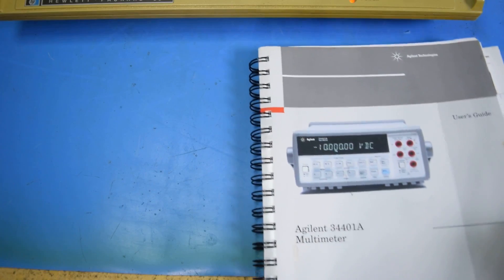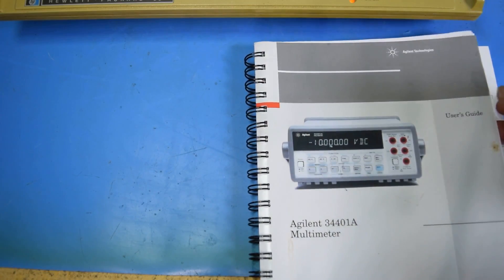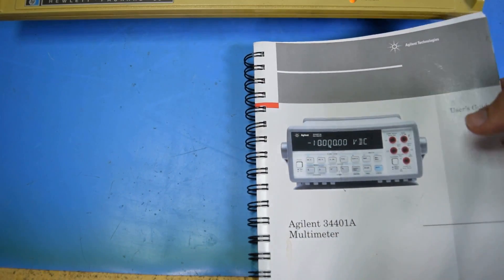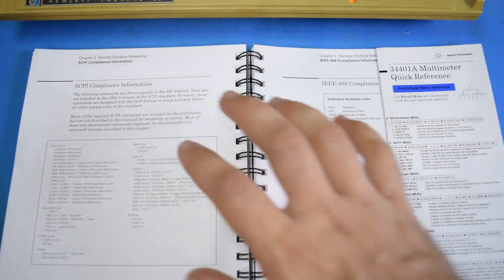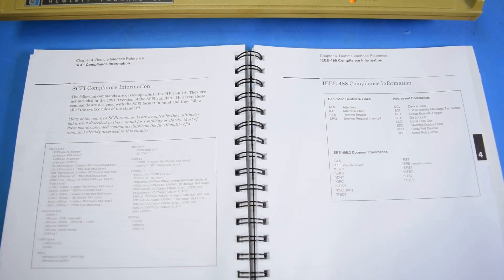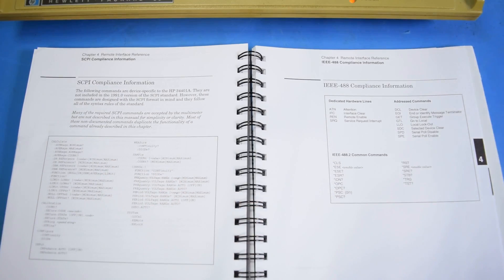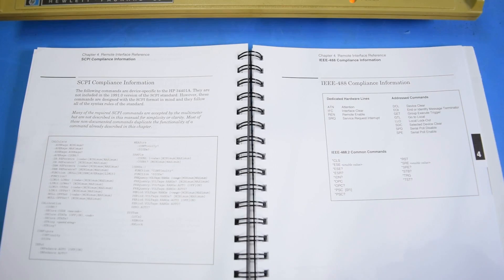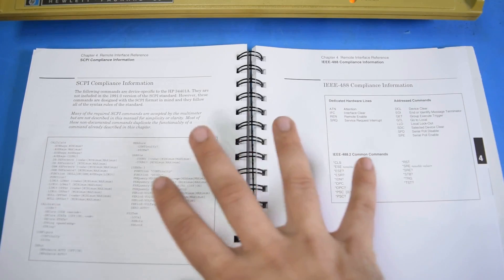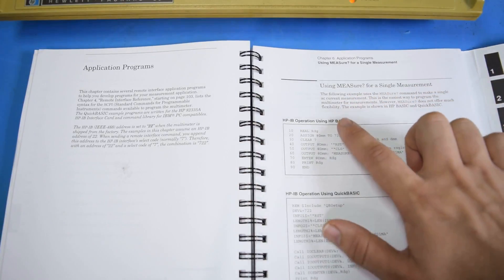Now in order to know how to use the multimeter with the computer, we don't have to look any further than the original manual. Since this is designed to be a remote controllable multimeter, it has all of the commands detailed here. The 34401A uses SCPI, or Standard Commands for Programming Instruments, as a communication protocol. That is a standardized protocol for communicating with test equipment like this. If we flip later into the manual, we'll see that this includes directions for using this with HP BASIC.